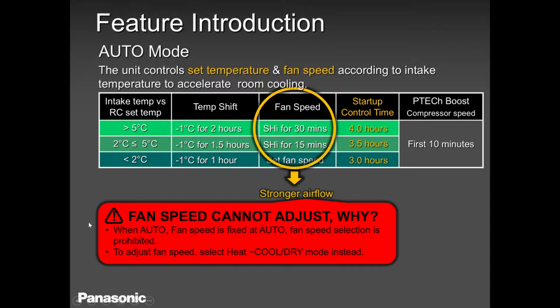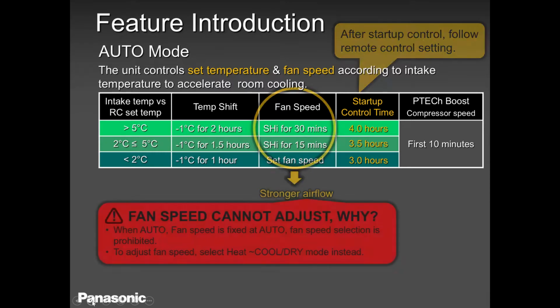So when a customer calls and says, "Hey John, how come my fan is going 5-10 minutes high and then low and then high and then low?", definitely there is something wrong with the outdoor unit, causing the coil to get hot and cold in a matter of 5-10 minutes instead of staying constant. Now it could be the refrigerant, it could be the sensor. You have to figure it out. If you don't think it's the sensor, then definitely there is something wrong with the refrigerant. Maybe sometimes a slightly kinked pipe, a restriction, name it.